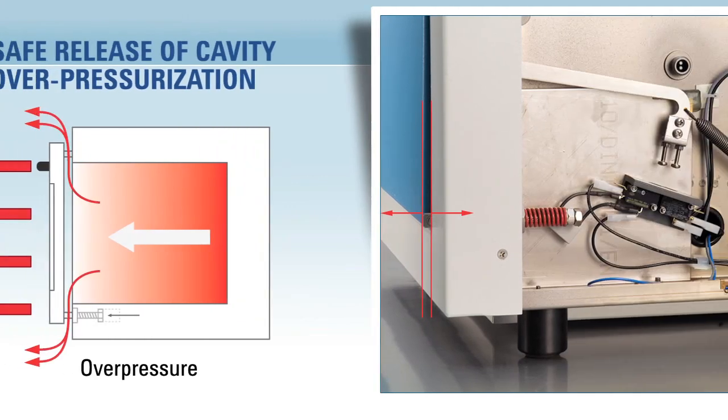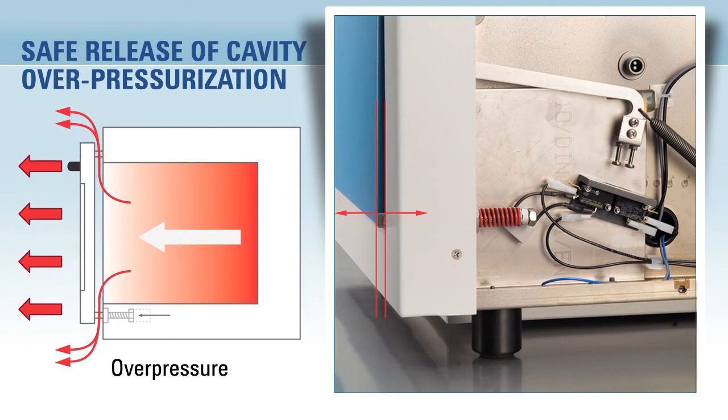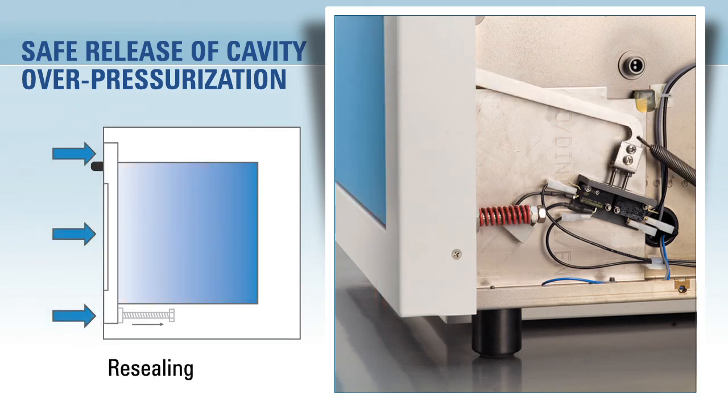The door features a unique pressure release system that is mounted on heavy duty steel springs. Should significant pressure be created in the cavity, such as a complete vessel failure, the door is designed to slightly lift from its mounting and reseal after excess pressure is released, a safety feature unique to Milestone.